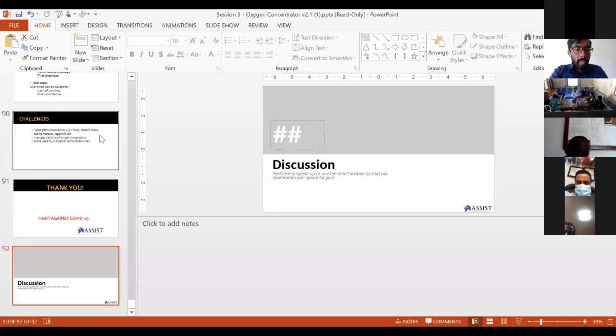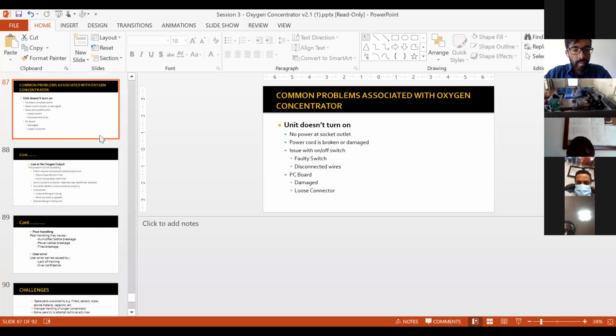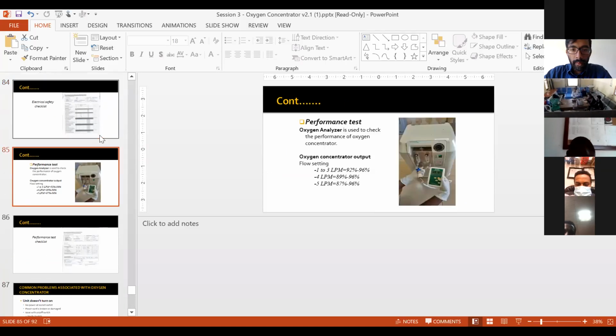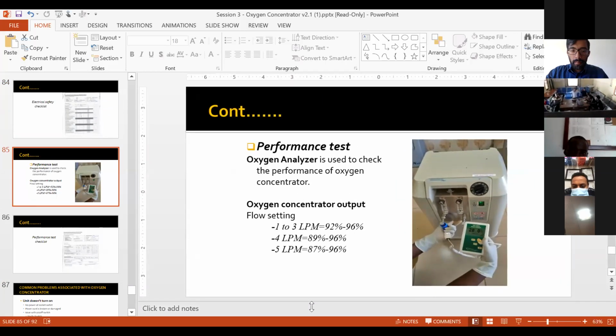Guna, I want to go back real quick and just clarify one thing on the PMs. When it comes to this unit here, do you want to go over that briefly? Okay, these are basically the oxygen concentrator flow output settings. So these are normally 1 to 3 liters per minute, and the purity can be 92 to 96, and 4 liters per minute can be 89 to 96, and 5 liters per minute can be 87 to 96.